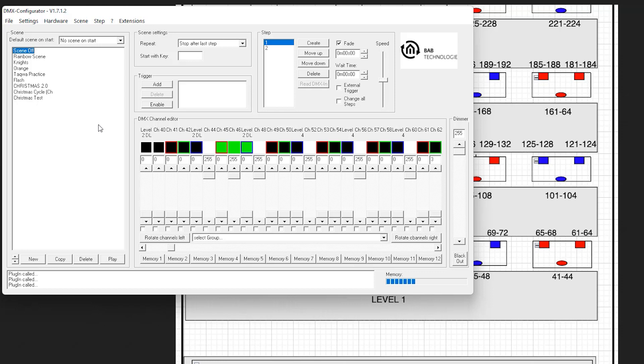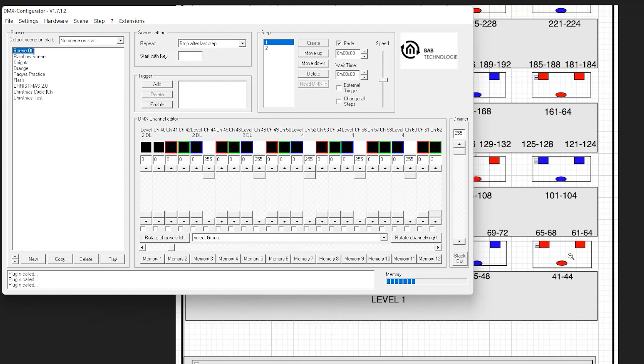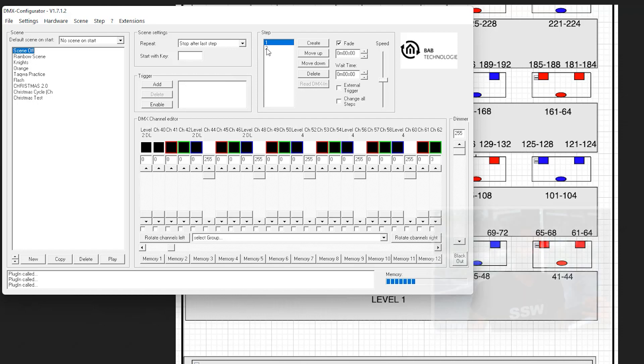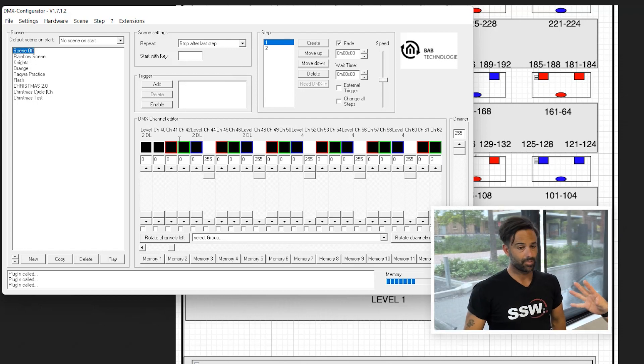So the next step, once we've got all the configuration, all the mapping going, we will go to our configurator. It's a DMX configurator. We set up our scenes within this. As you can see, 41 to 44 is our first down light. Now, how does this map to down the bottom right, the lights? This is our first light that we're going to configure, down light. First address is channel 41. We're working with the scene off at the moment. The first step which shows here will be off.